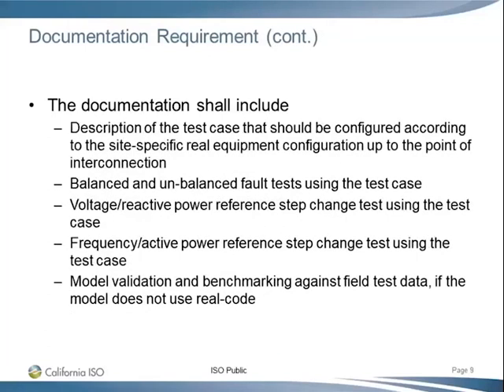Yeah, so the documentation should also include a description of the test case and how you have configured it according to the site-specific equipment. You should tell us if you have scaled it up to match the number of inverters, for example, and set the parameters in a way that matches your actual plant. Then in the documentation, you should also include some tests. It's not just the document you get from the manufacturer. Actually, you have run this PSCAD model for your plant. So we'll ask you to show some balanced fault test using the model, and also show a voltage reactive power reference step change test and a frequency active power reference step change test.